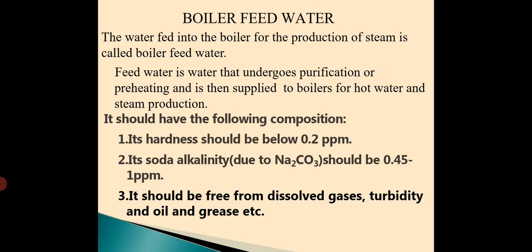Now let us go into the concept of boiler feed water. The water which is fed into the boiler for the production of steam is called boiler feed water. Feed water is water that undergoes purification or preheating and is then supplied to boilers for hot water and steam production. It should have the following composition: its hardness should be below 0.2 parts per million, and its soda alkalinity due to Na2CO3 should be 0.45 to 1 parts per million. It also should be free from dissolved gases, turbidity, oil and grease etc.